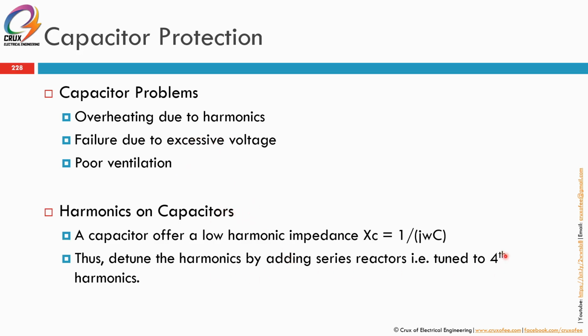In this case, the 4th harmonic. This is most probably for a VSD with a 6 pulse rectifier, which will produce 6 pulse plus minus 1, that is the 5th and 7th harmonics. So there will be high 5th and 7th harmonic content in that system, and you detune your capacitor bank to the 4th harmonic. Okay.